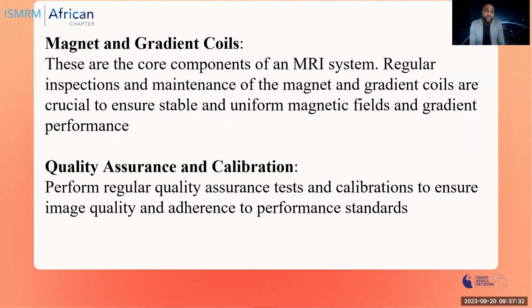Quality assurance and calibration. It is very important during the preventive maintenance stages to ensure that the quality assurance, which I call QA, for the system is done, and to ensure that the system is still in specification with the manufacturer standard. Also, frequent calibration, especially during the preventive maintenance, is a must during these MRI maintenance phases. This in turn helps to ensure that the system is in a very good state for operation, and also we can guarantee the quality of the image after a diagnosis process.